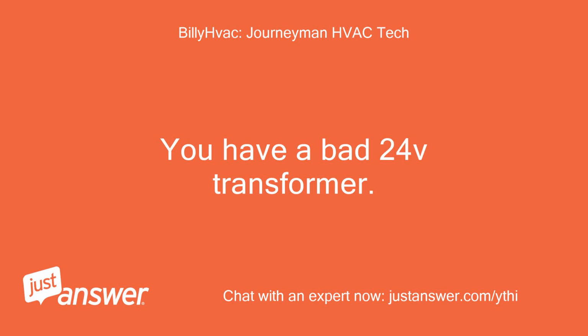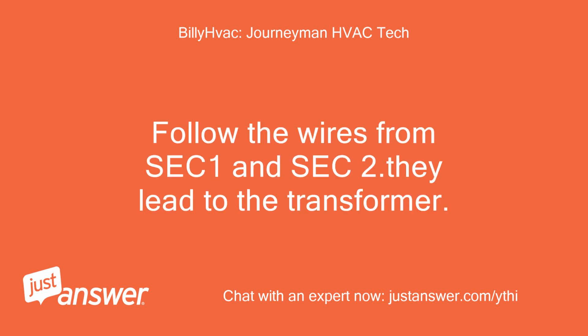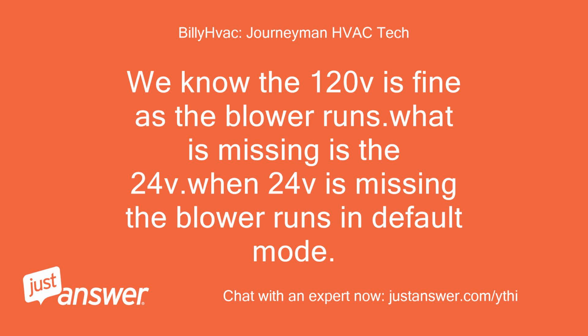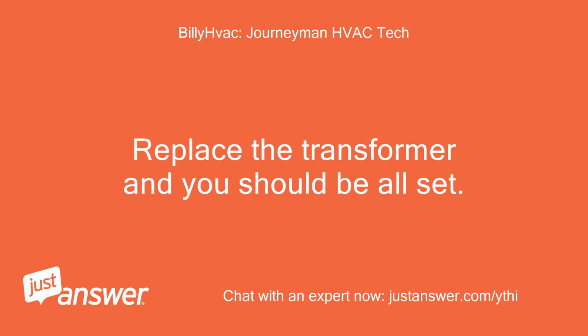You have a bad 24V transformer. Follow the wires from SEC1 and SEC2, they lead to the transformer. We know the 120V is fine since the blower runs. What's missing is the 24V. When 24V is missing, the blower runs in default mode. Replace the transformer and you should be all set.